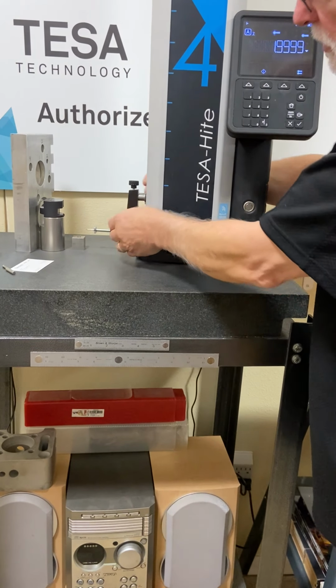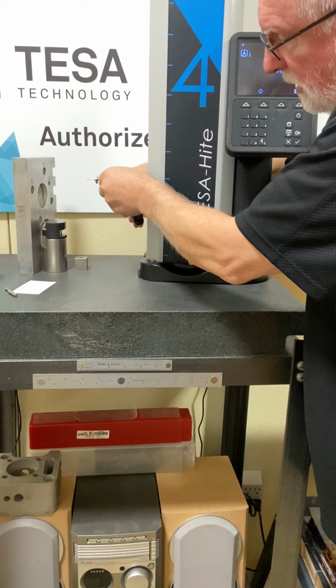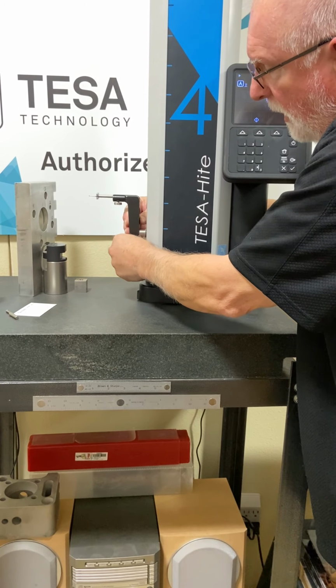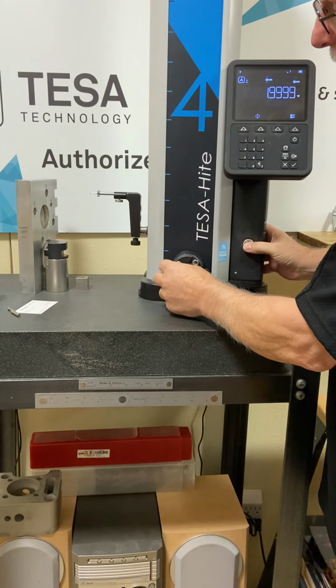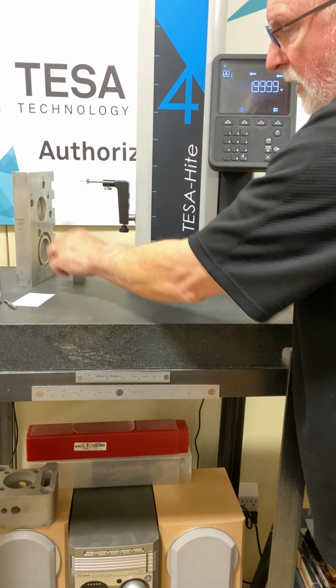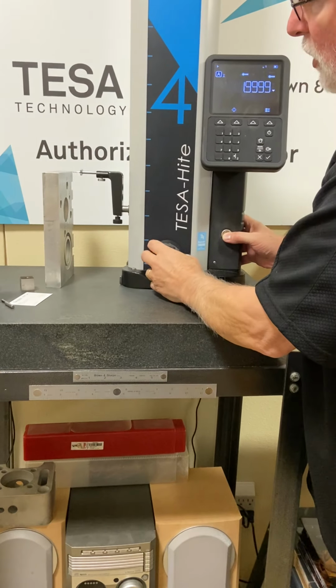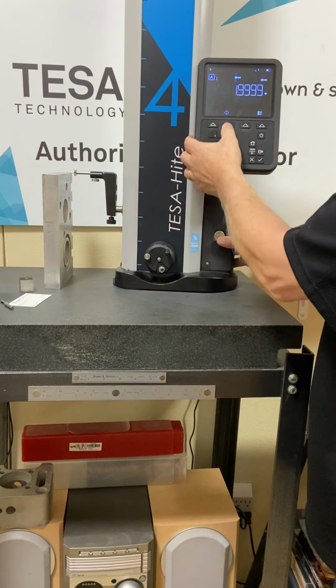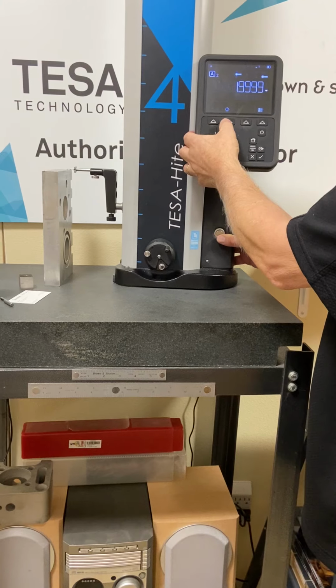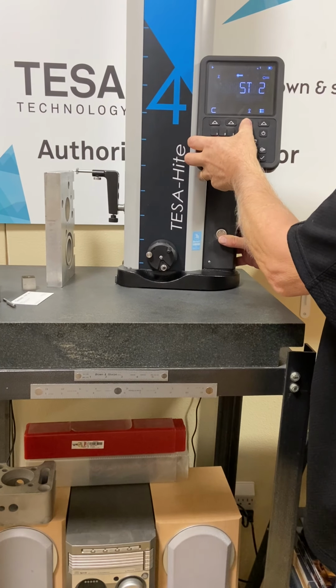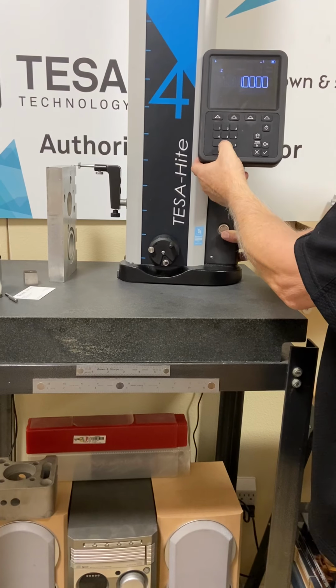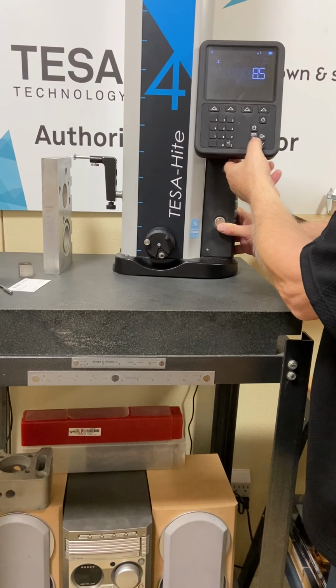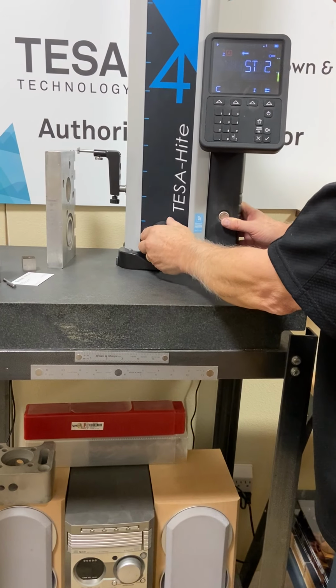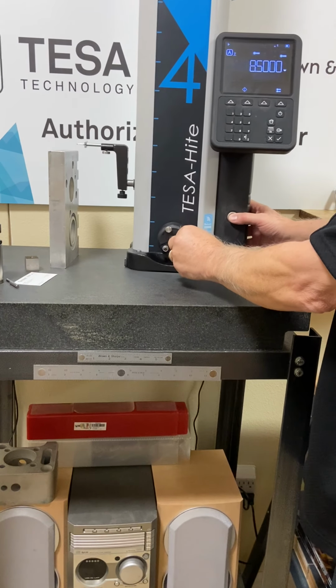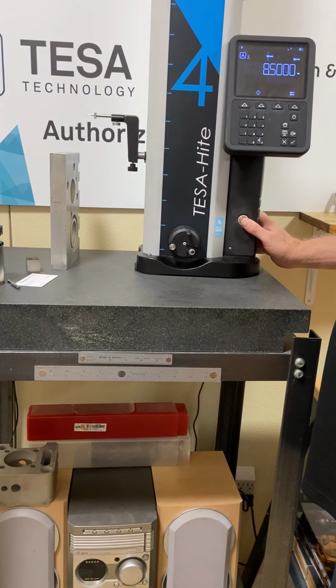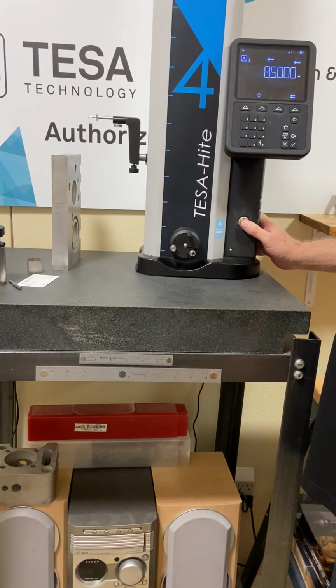So now the other reason you'd want to do an indirect reference or an offset is I can rotate the arm. This is a 3.5-inch probe arm on here. And if I have a known height, let's say this part right here is 8.5 inches, because I'm still going to want the surface plate set at 0. So I can go over here, I can do my indirect reference, and I'm going to key in 8.5 inches. I'm going to hit the enter button, and I go down and touch off of it. And now my surface plate is still at 0, but I've got an extra 7 inches out of any of the height gauges that you use.